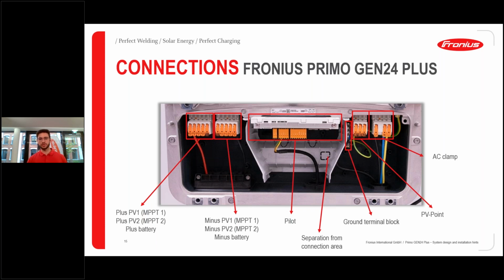And then right next to the grounding terminal, we see the PV point, which is actually the first backup solution that is standard integrated again with every product. And it's this single phase connection point. I will explain a little bit more later on how this is functioning, but basically the PV point is the standard backup solution available for every Primo GEN24 Plus device. And right next to the PV point, we can see the AC clamp here, in case for the Primo also the single phase connection.